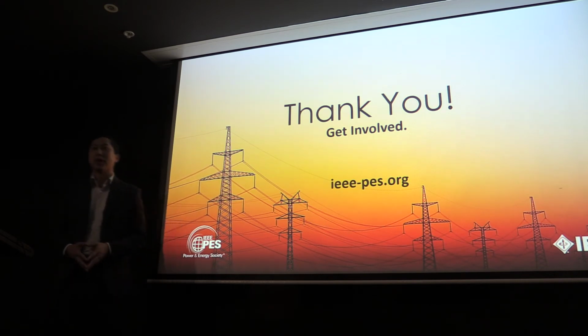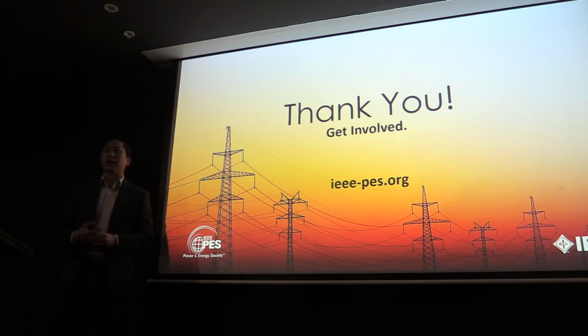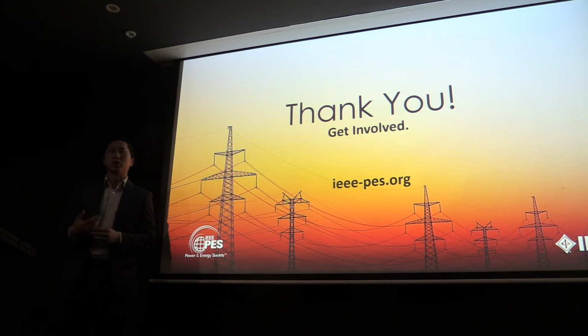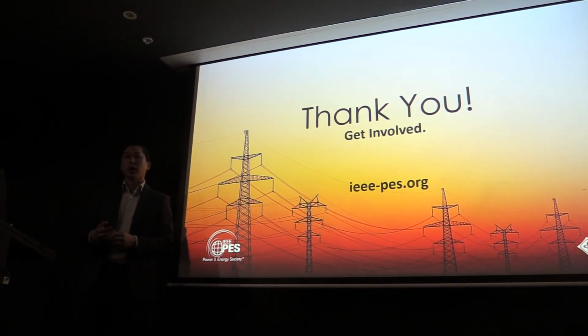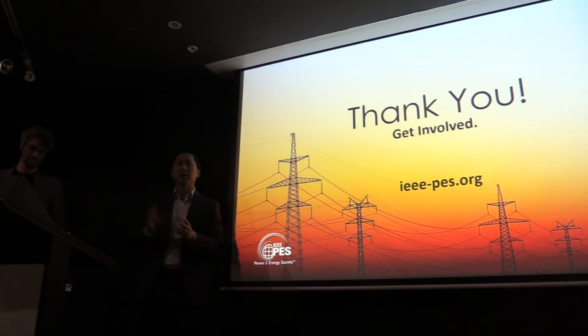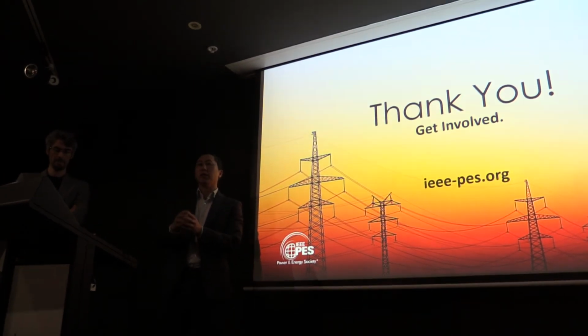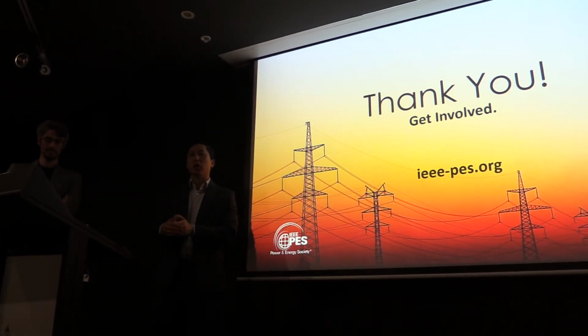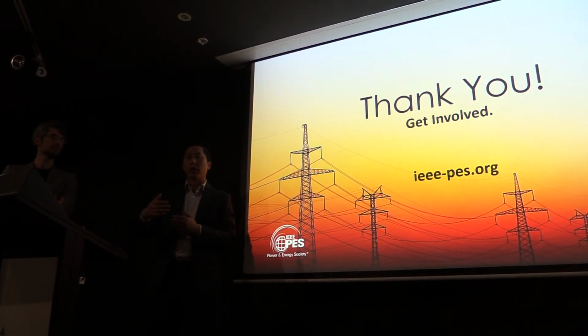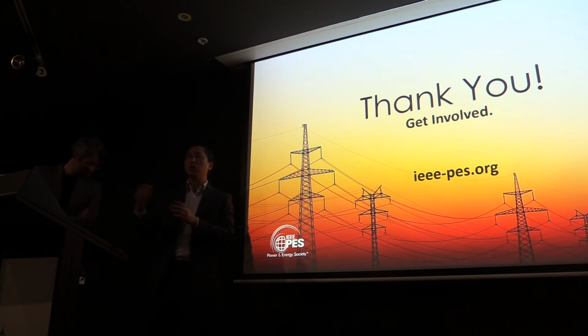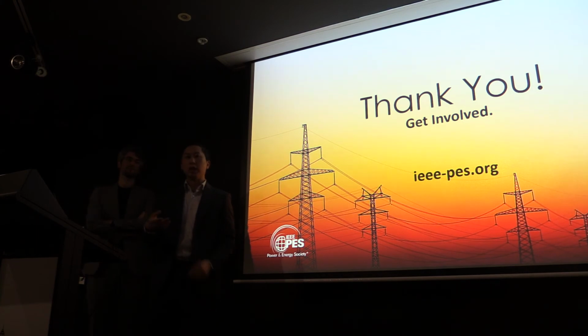There is a trade-off between fast frequency response and inertia, and it gets you some way. Definitely, the lower your inertia is, the more valuable fast frequency response is. You're well aware that the new reformed market has speed factors in place, which will incentivize faster responses at low inertia times and high contingency times. If you kept the headroom, I think in the new market it should be possible for a renewable energy plant to provide spinning reserve if they could prove their headroom was able to provide it, and they would be given a fairly high speed factor if they can do it very quickly. If we're talking about a solar farm, if you can ramp up within a second, then surely you get a high speed factor.